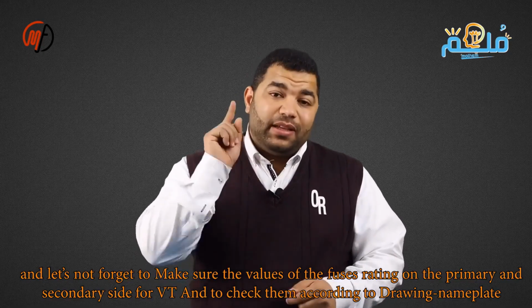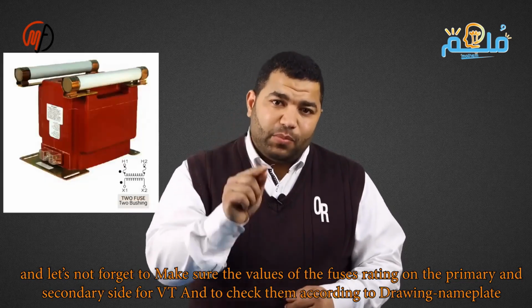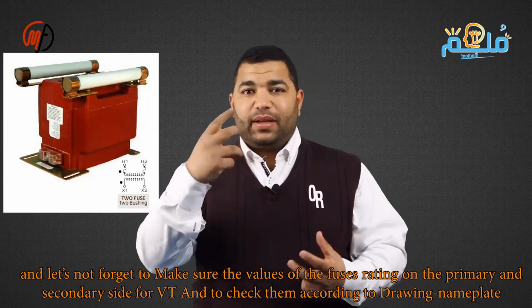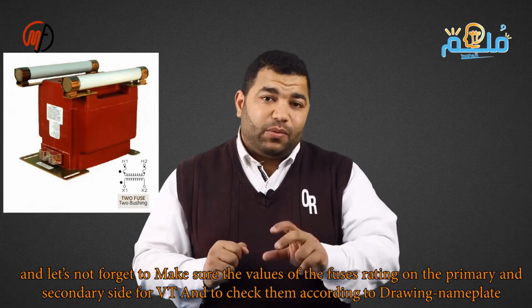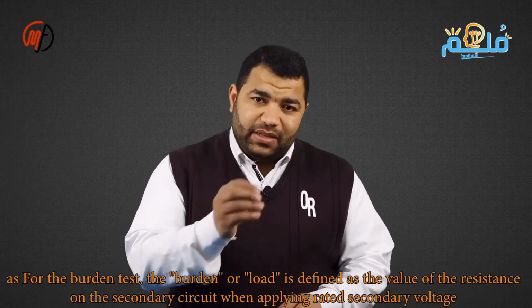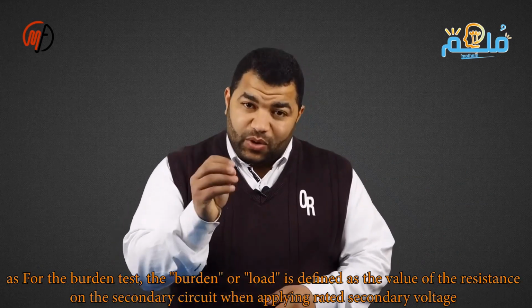Let's check the fuse ratings on both sides of the VT and verify them with the drawing. The burden test defines the burden as the resistance on the secondary circuit with the rated secondary voltage expressed in ohms, amperes, or apparent power in volt amperes.